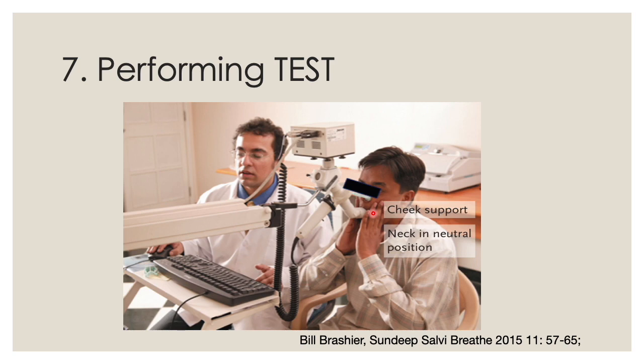So when we start the test, we just tell the patient to perform normal tidal breathing in a resting state. We perform the testing for around 30 to 45 seconds. And when we are doing this, we are actually giving almost 120 to 150 sound impulses and pushing them into the lung. And from these, we will determine the reactance and the resistance at frequencies 5 to 20 Hertz.